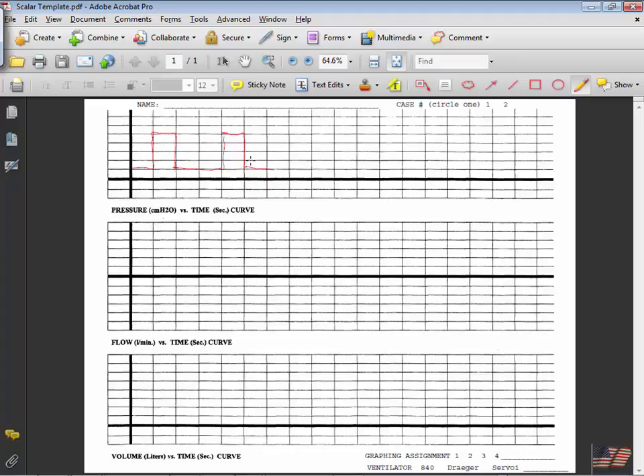Okay. Again, can't see auto-PEEP from the pressure tracing, you can only see it from the flow tracing. What does the flow curve look like in auto-PEEP, or with a pressure-based breath? The erect one. That one where it goes up and then it squiggles down. Well, kind of, sort of.